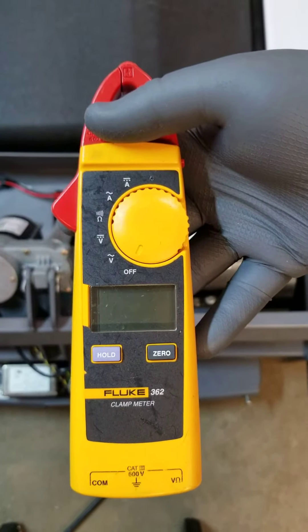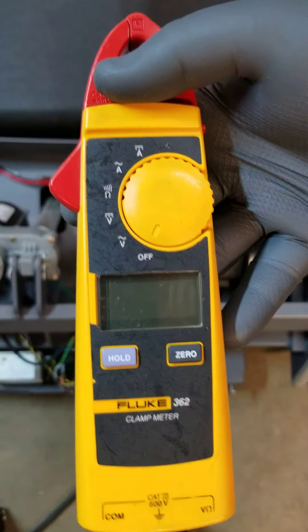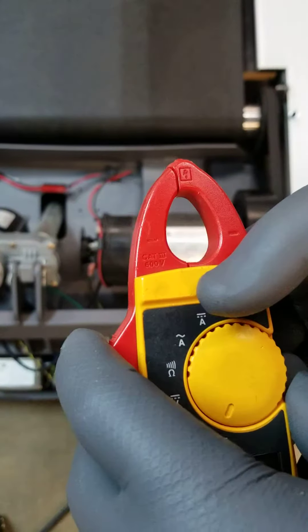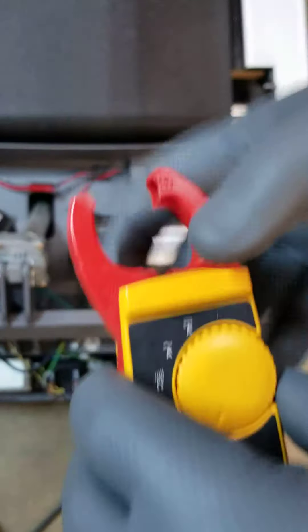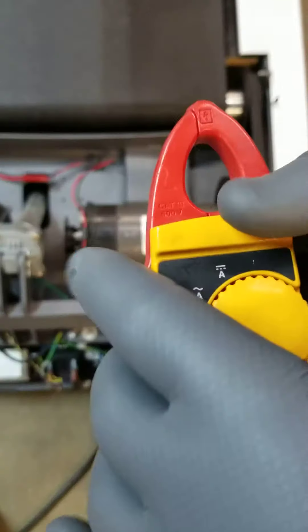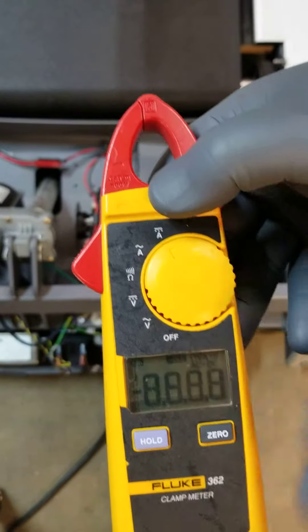What we're going to do right now is an amp draw with our Fluke 362 meter, like we've been using. We get to use this mechanism to do our amp draw. We're not going to clamp on the wire like that, even though this is called the clamp meter — we just kind of loop the wire through.